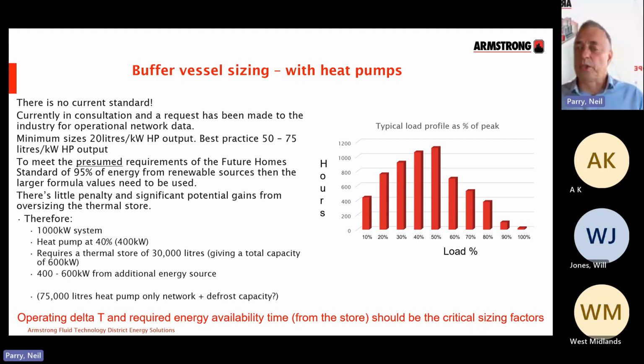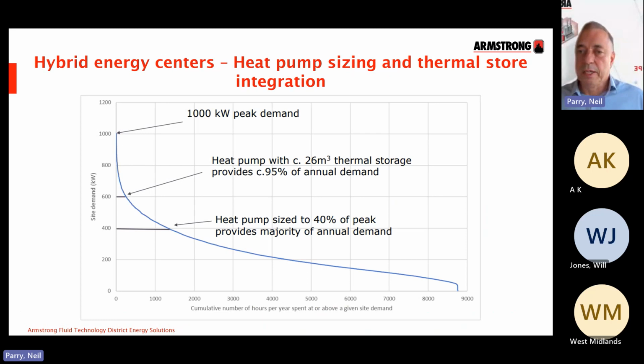So you can see what that looks like in a graph here. This is the demand curve, if you like, and the heat pump size, just 40% of capacity, covers all this time here, and that's why you're hitting 90-95% of demand. Thermal storage is covering this area, and you can see there's a really small area here where the peaking plant is providing the additional energy.